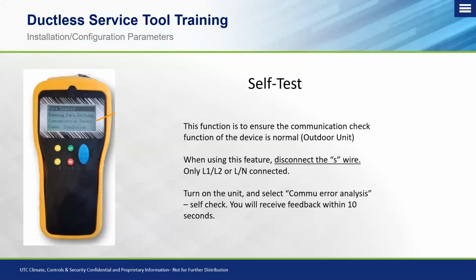When we're using this feature, we want to make sure that we disconnect the signal wire from that particular zone that we're connecting to. So we only have L1 and L2 or L and N connected, depending on what type of power system we're dealing with. Now, there's a signal wire that hooks up to our indoor unit from the tool. We want to have our L1 and L2 connections from the tool connected and piggybacked off of the L1 and L2 that's currently on the bus bar, because we need to power the tool.